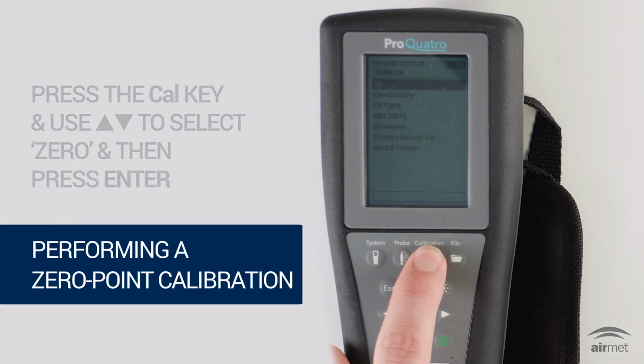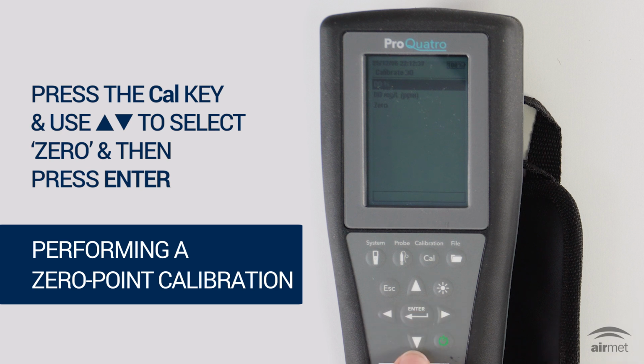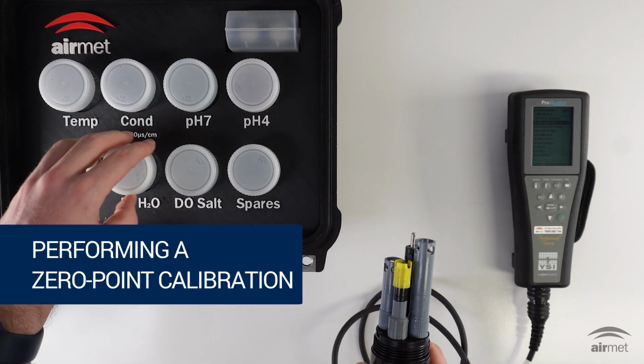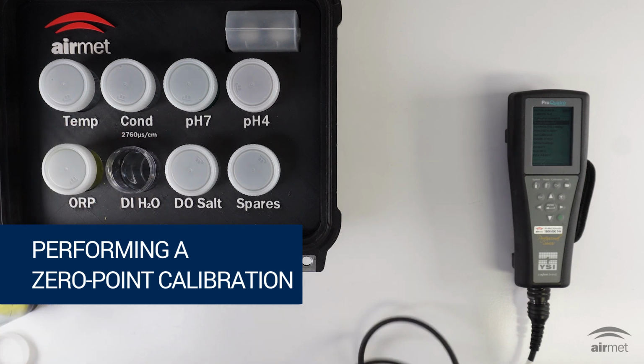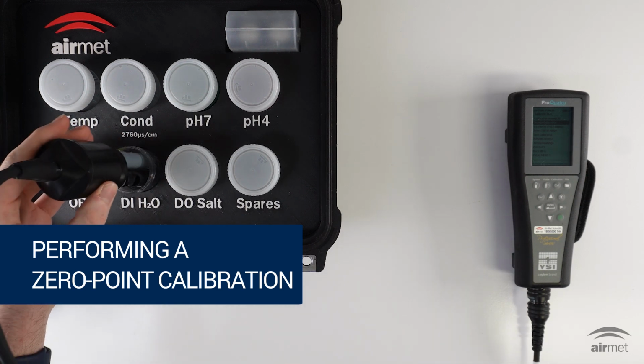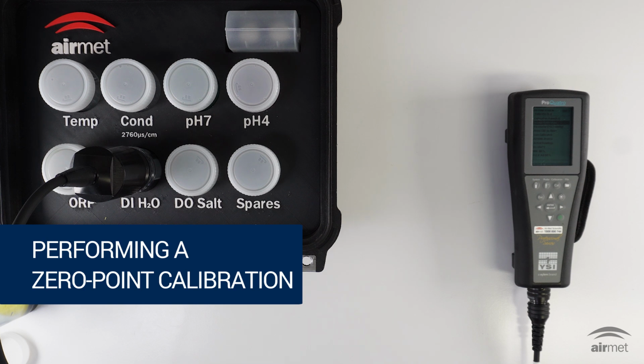From the calibration menu, highlight DO and then select DO 0. Insert the probe into the zero oxygen solution. Observe the reading for stability. This can take around 1 to 2 minutes.